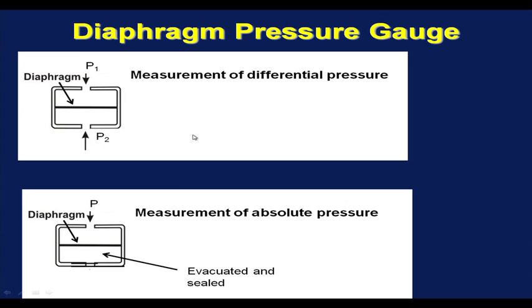This schematic shows how we can measure differential pressure with help of a diaphragm element. We have a diaphragm here. So, this diaphragm divides this into two chambers. In one chamber, we apply pressure P1, the other chamber we apply pressure P2. So, the movement or the deflection of this diaphragm will be dependent on P2 minus P1. So, this deflection can be read again by using a pointer and scale. We have to attach a pointer and scale with this diaphragm through appropriate mechanism, and the deflection of this diaphragm will be a measure of the pressure differential P2 minus P1.